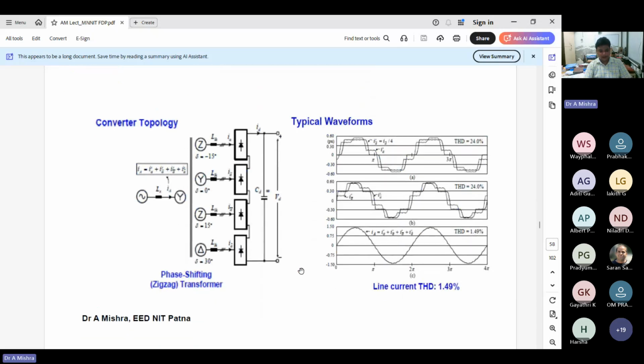24 pulse rectifier, again you can find as the one is the zigzag, star, zigzag. This is just about creating the phase difference. The first one is creating minus 15 degrees. The second one is 0. The third one is plus 15. The fourth one is 30 degrees. So based on the combination, remember here 4 converters are used, but all 4 converters are independent 6 pulse converters.